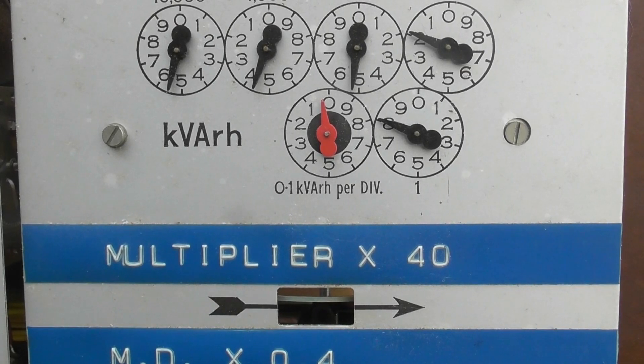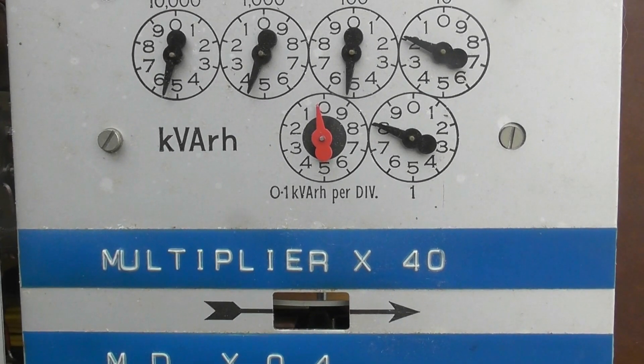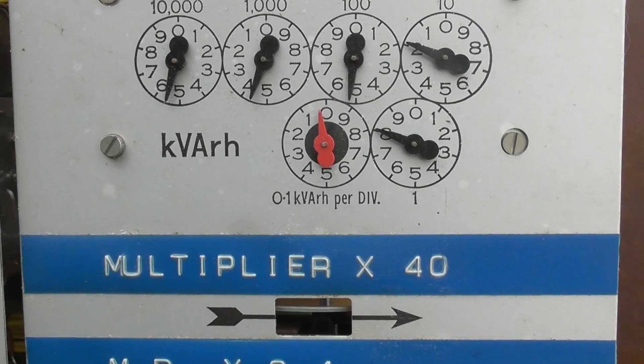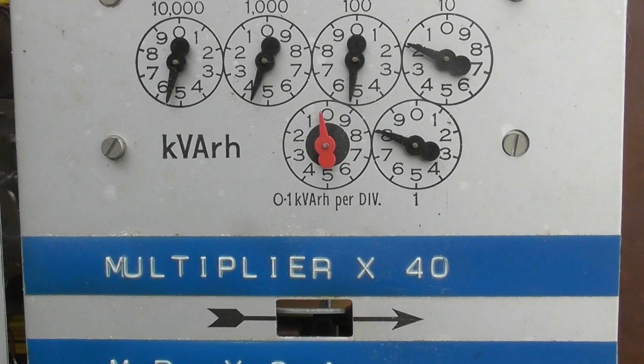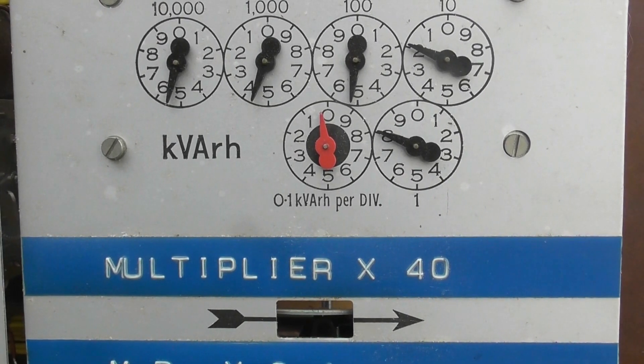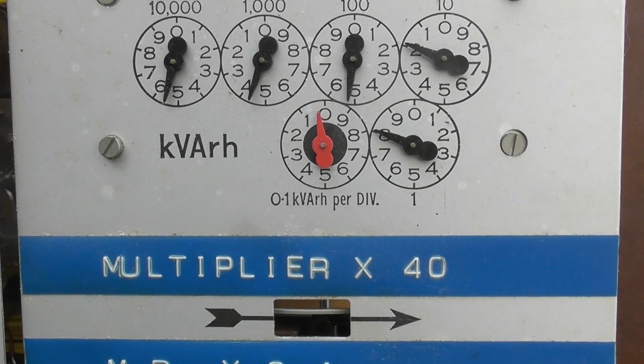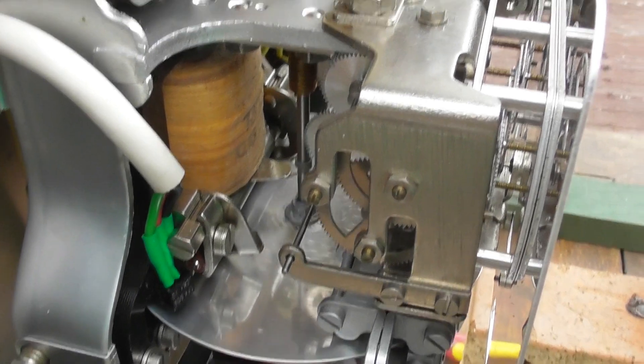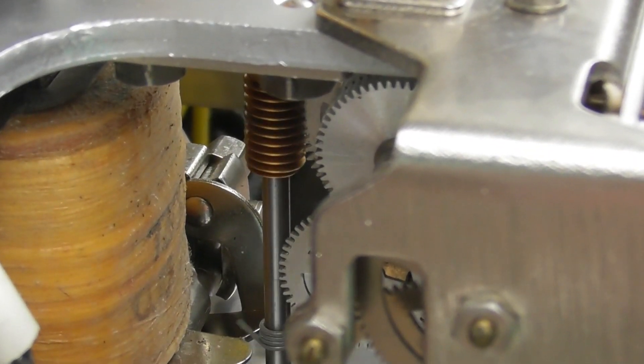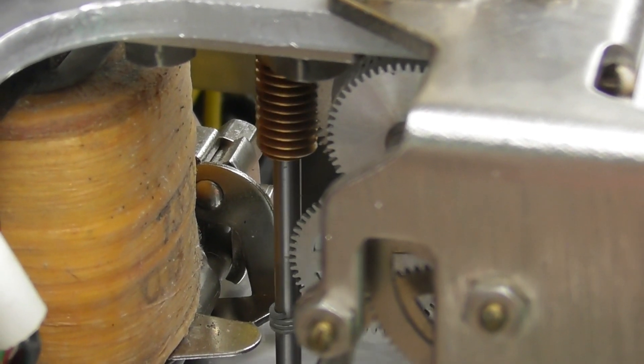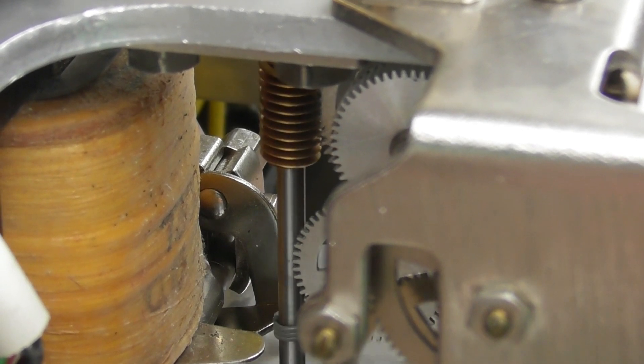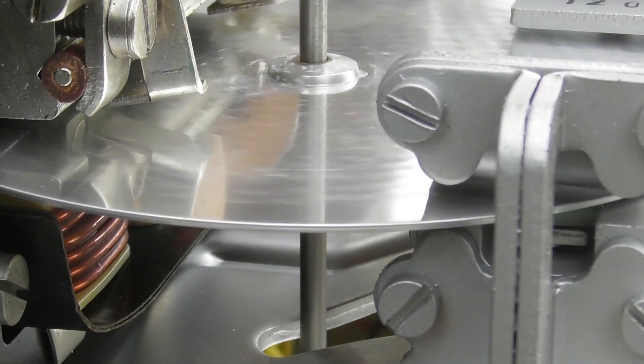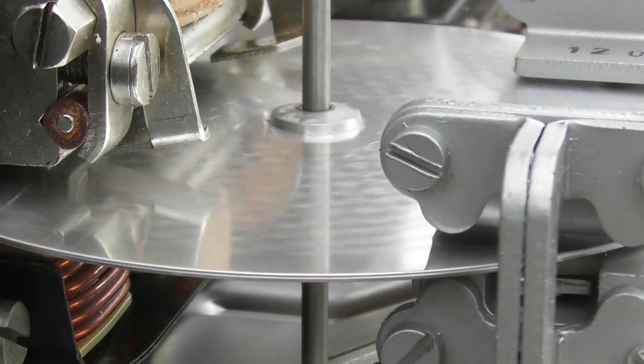So the KVARH meter part is running slowly because there's a little fan motor in the heater. If the load becomes more inductive in a factory and the power factor will drop, the reactive part of the meter will run faster and the active one will slow down. Here you can see the disc speed - reasonable speed. You can see a bit of wobble in the disc shaft and a bit of squeak sound as well. The meter has been dumped I think.